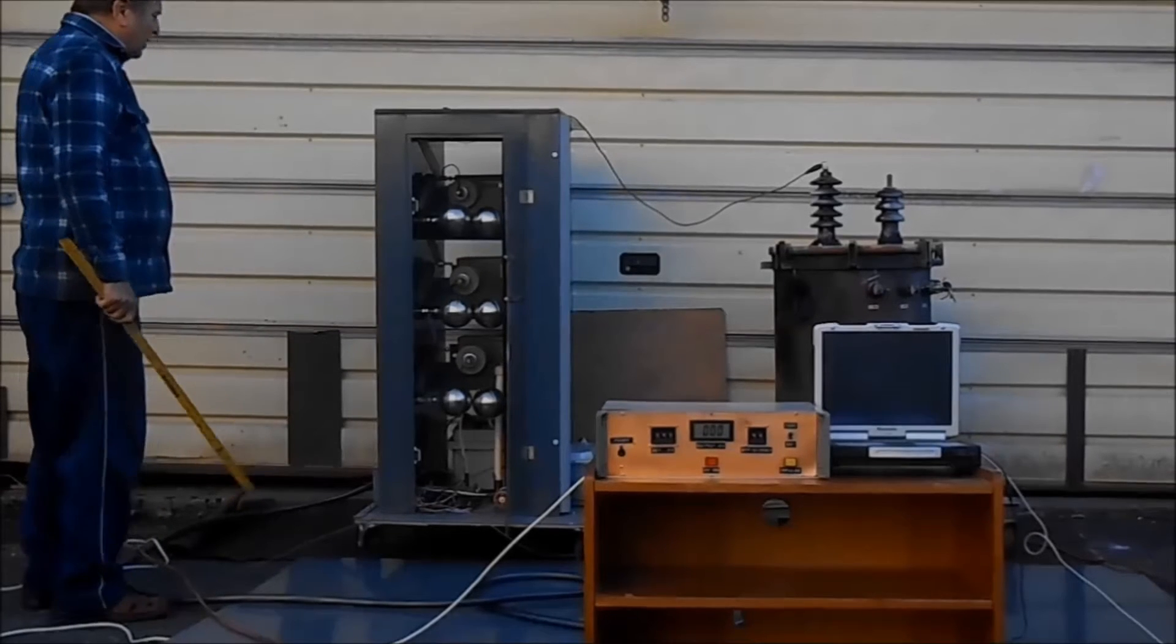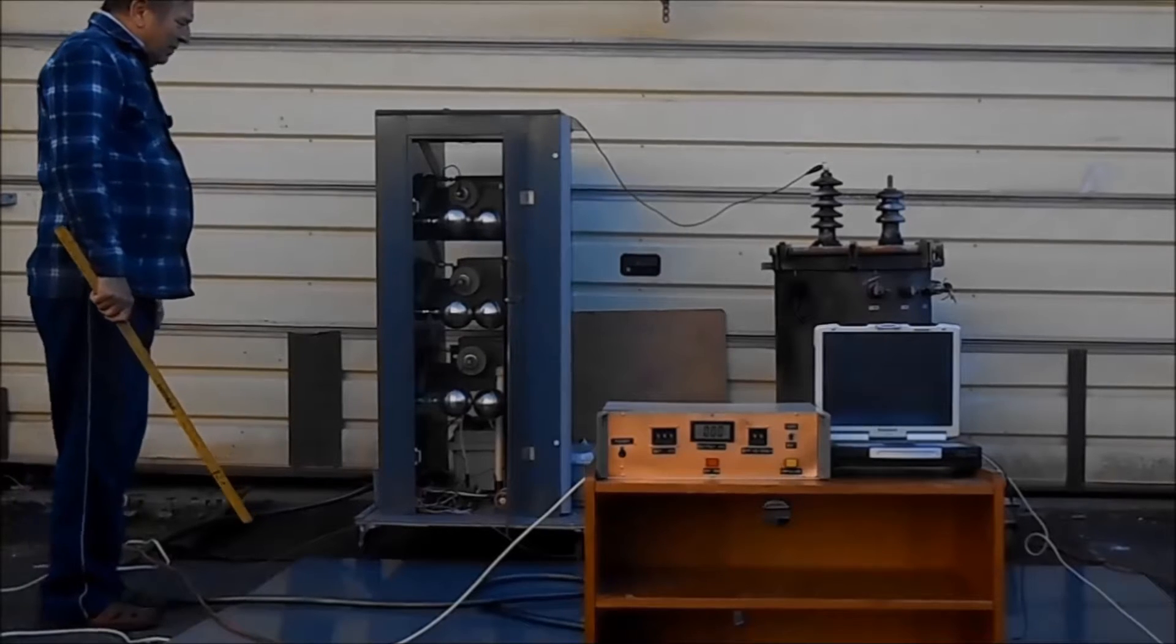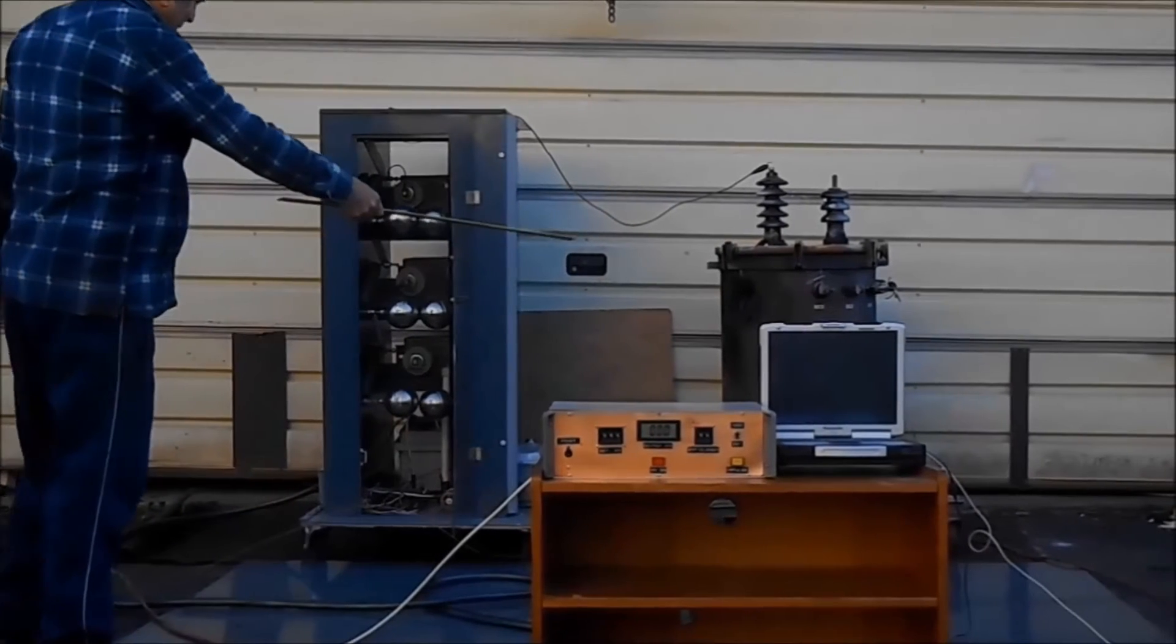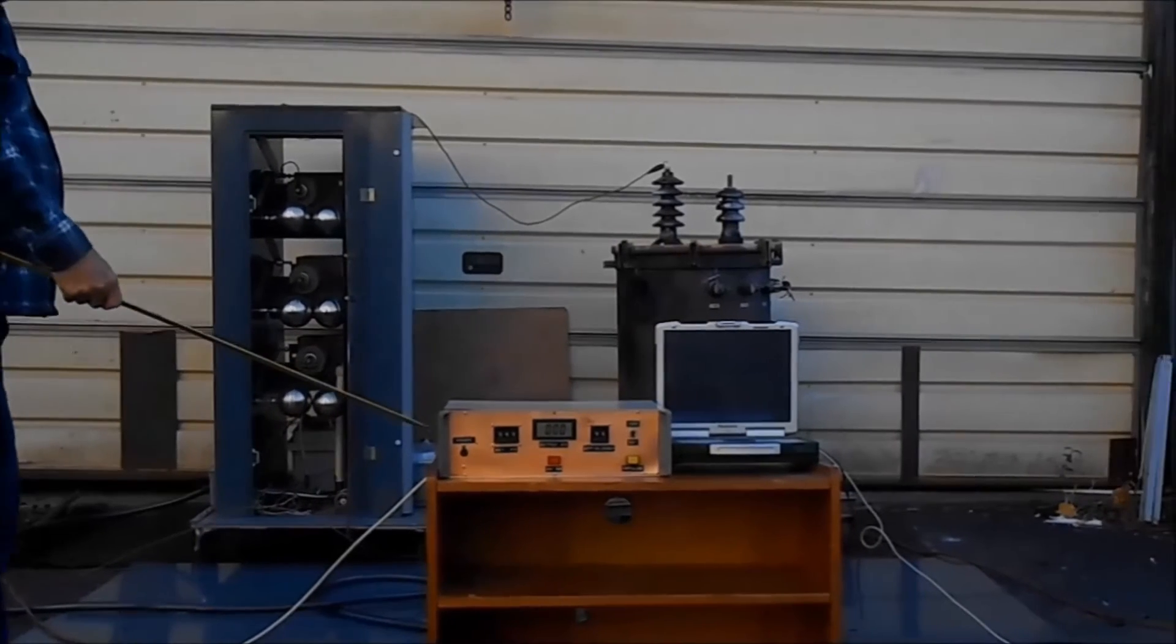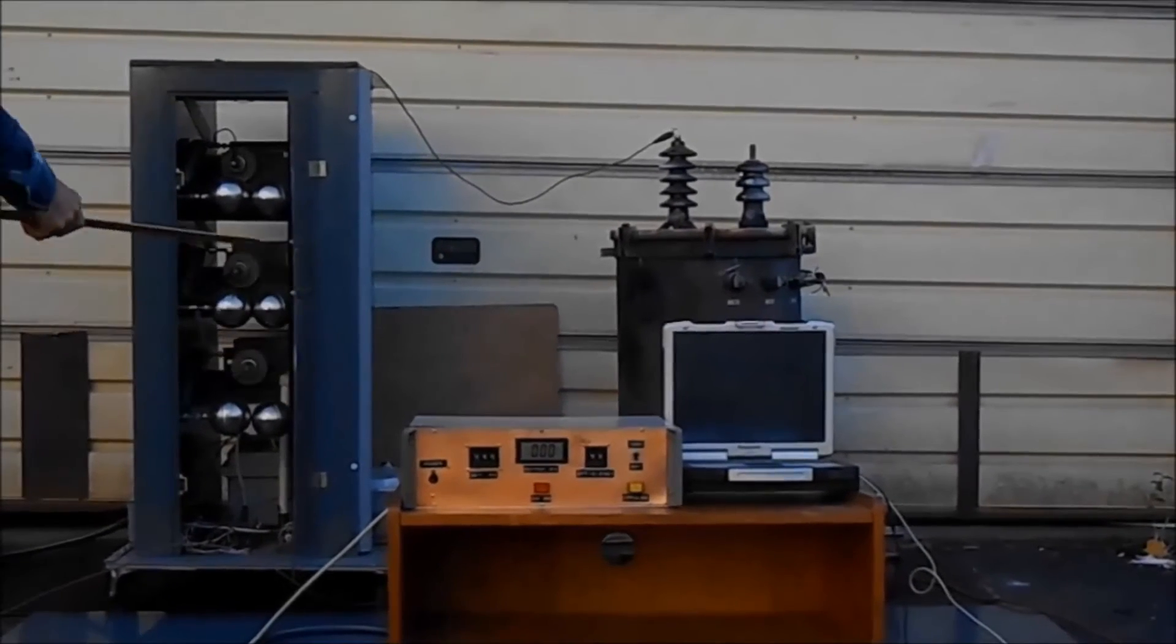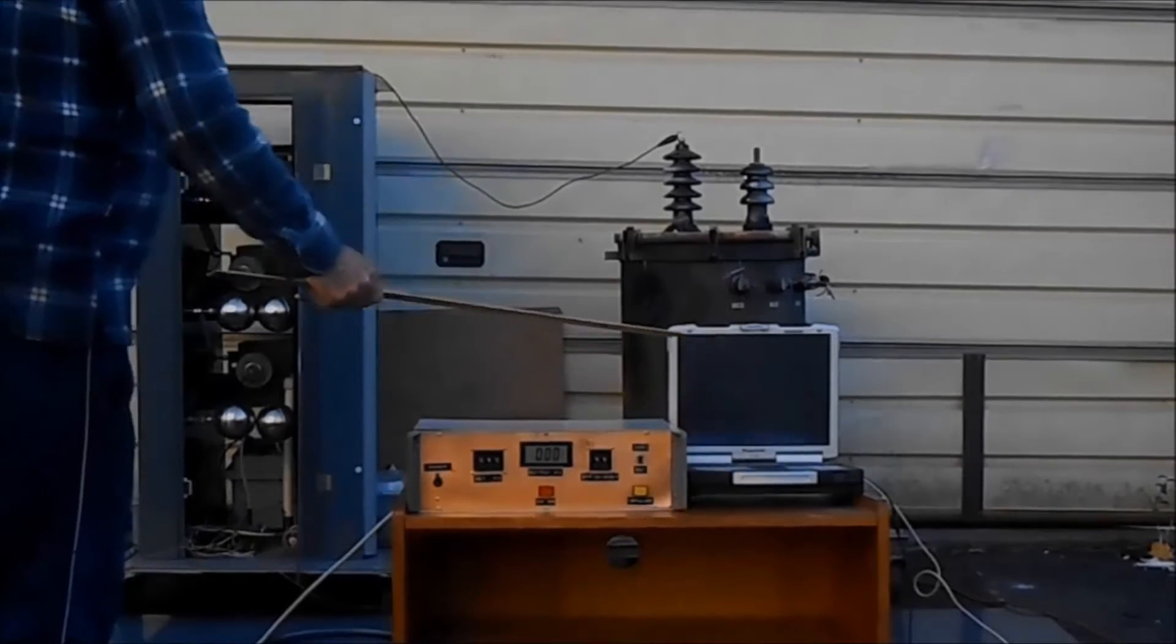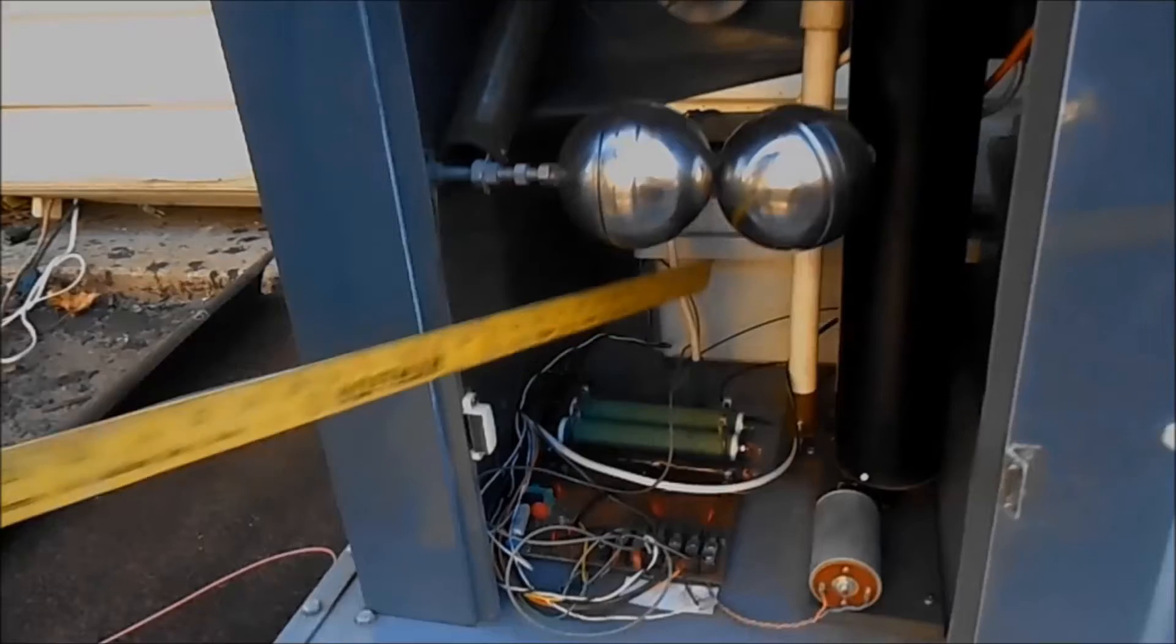We are going to impulse test a power transformer using an integrated impulse generator with a smart controller. We have a digital recording system for the waveforms and it's working through a laptop.